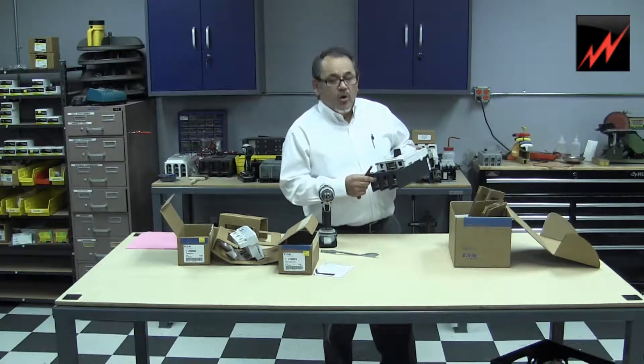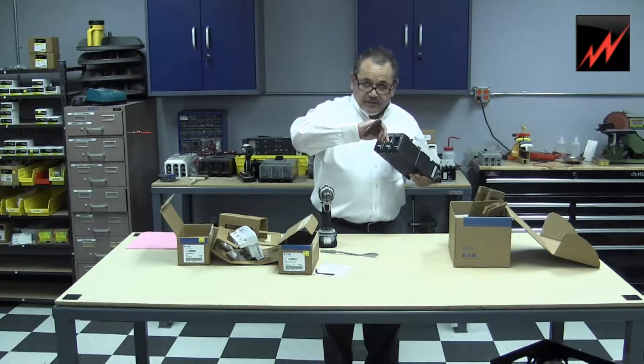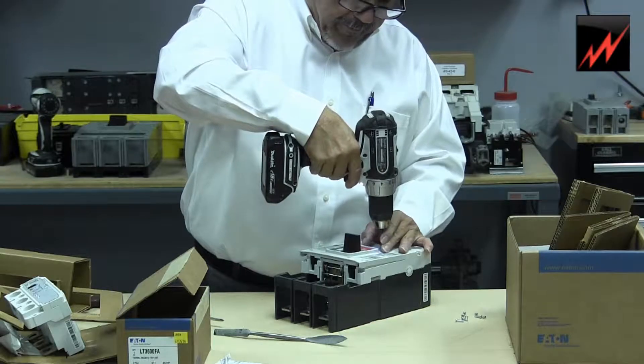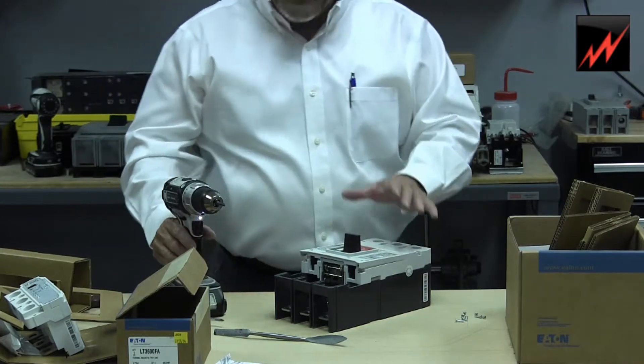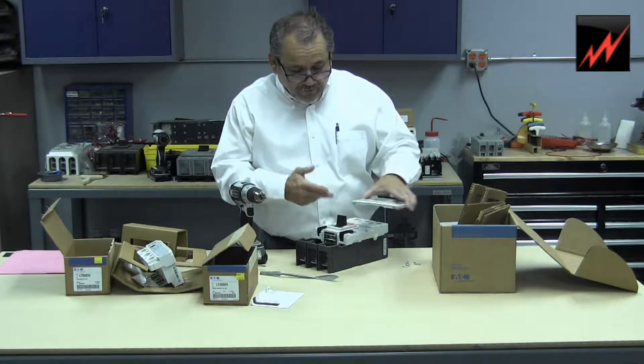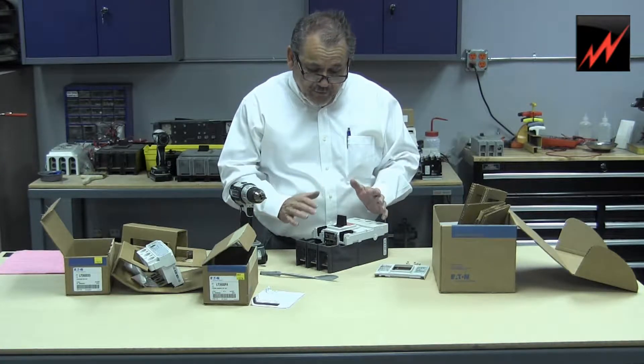As you can see, it's starting to bind right there. Now, we've shown you the hex bit and the access points that are unique to this system. So what we need to do now is remove the lid. We've taken out two, four, six, eight screws off the lid. As the screws are coming out, you'll hear the trip mechanism kind of release.